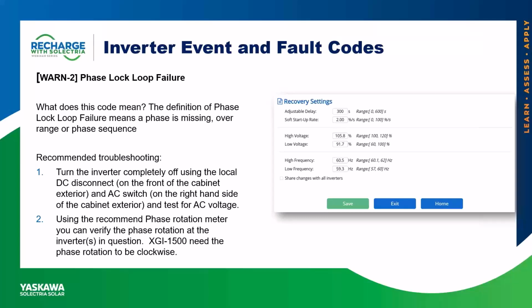Possible components that could be an issue, especially if all the AC voltages are lining up and you have confirmed that rotation for the phases is clockwise, would be the K2 contactor, the DSP board, or the interface board. The K2 contactor needs to close for the inverter to see voltage. The DSP board needs to send control voltage to tell the K2 contactor to close, and the interface board is responsible for displaying voltage on the GUI.